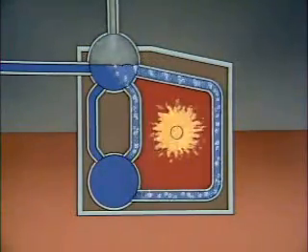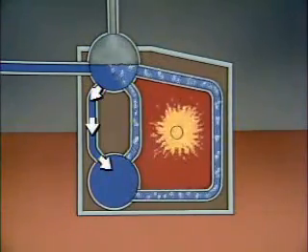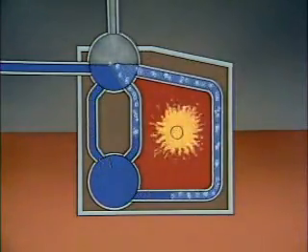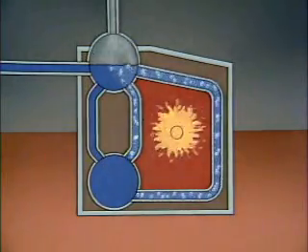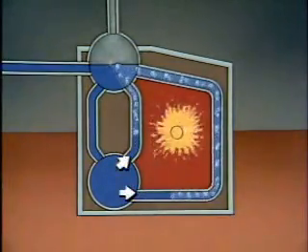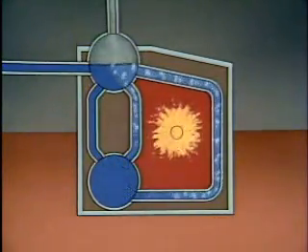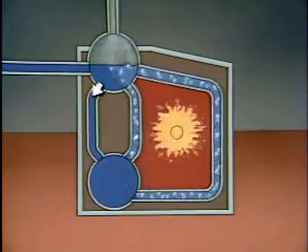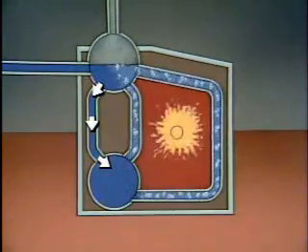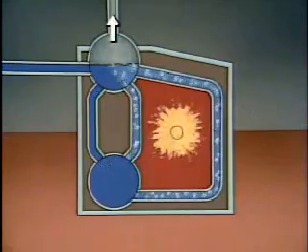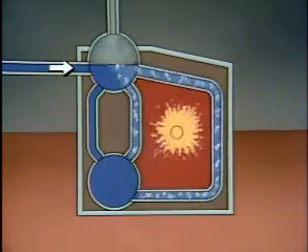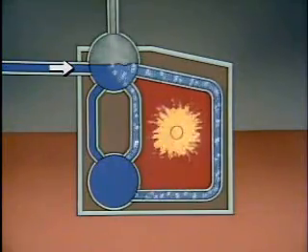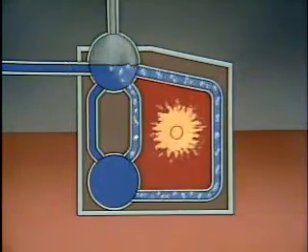As a result, the heavier, cooler water flows downward into the lower drum, and the lighter steam-water mixture flows into the steam drum. Then, as the cooler water is heated, it too becomes lighter. It rises to the steam drum and is replaced by cooler, denser water. The steam flows to the plant through the steam outlet, and the water level is maintained by the water flowing through the feed water inlet. As long as combustion takes place, natural circulation continues.